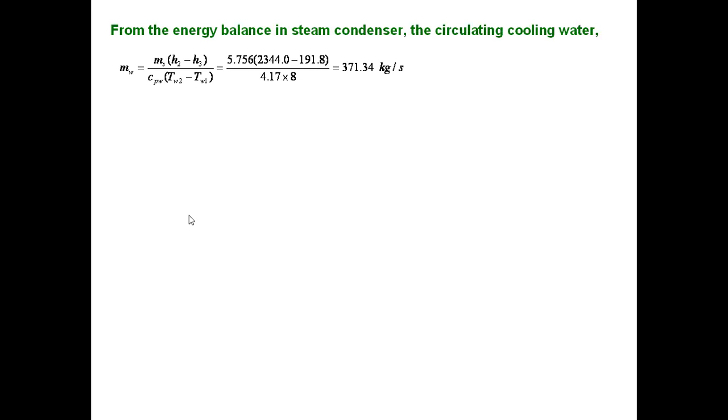To find the irreversibility loss associated in the condenser, first of all, we need to determine how much amount of circulating water is required in the condenser. From the heat balance in the condenser, Ms·(H2 minus H1) equals Mw·Cpw·(Tw2 minus Tw1).